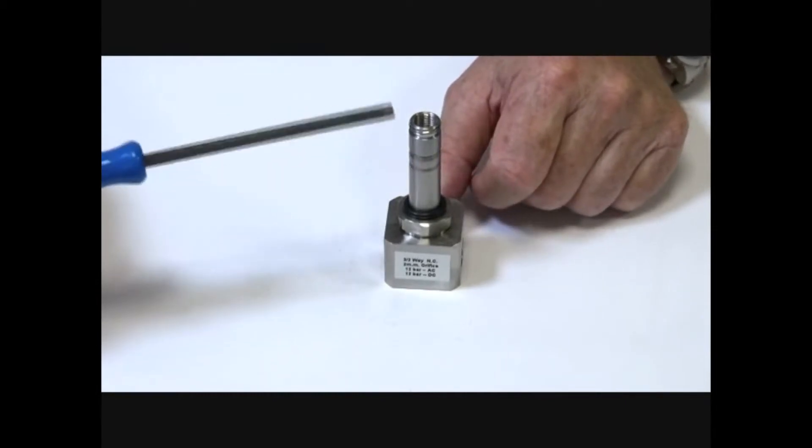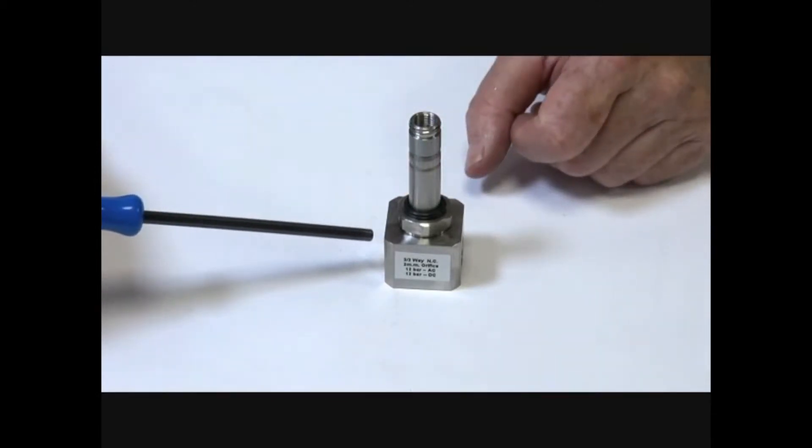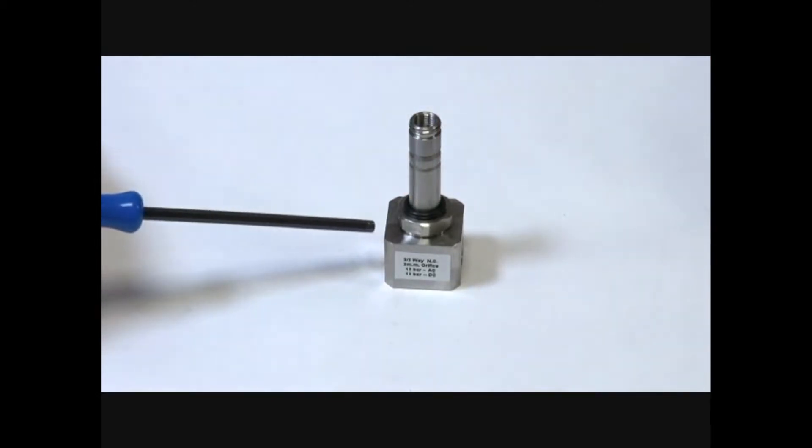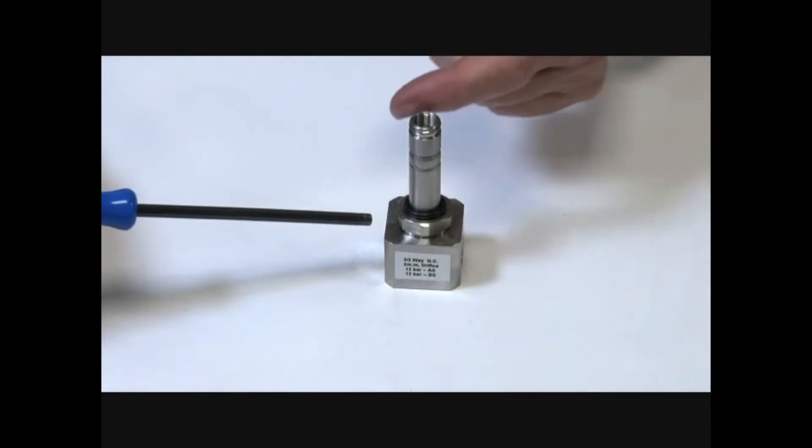When it's energised, the armature comes up, blocks off the top port, and you get port one and two connecting. Supply flows through when energised, and downstream exhausts through the top when de-energised.